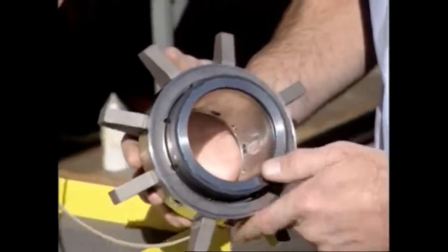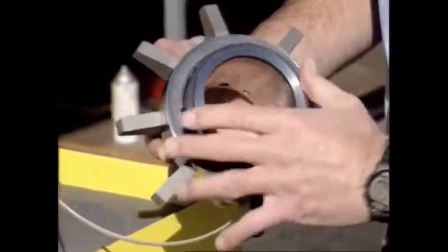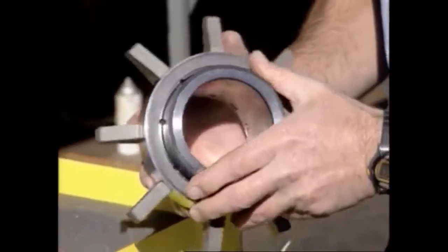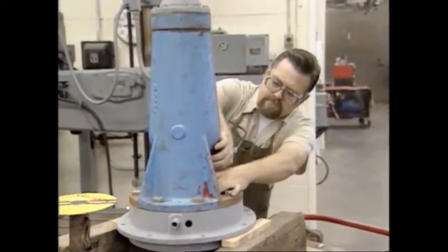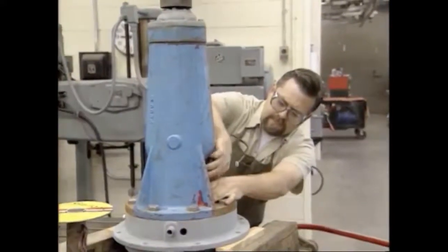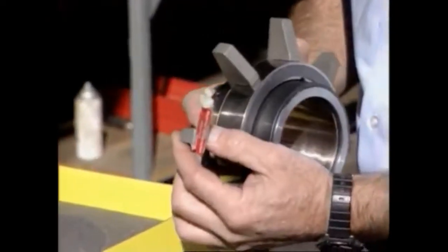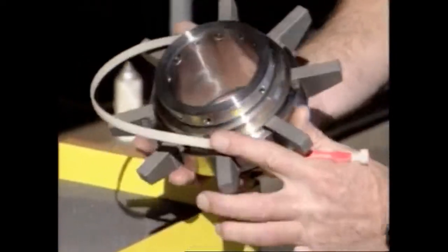Many pumps use mechanical seals in place of packing. Mechanical seals perform the same job as packing, that is, to prevent leakage between the pump casing and the shaft. Like packing, they are located in the stuffing box where the shaft goes through the volute. They shouldn't leak. That's one of the reasons why mechanical seals are gaining popularity in the wastewater field. Mechanical seals have two faces which mate, preventing water from passing through them. One half of the seal is stationary, and the other half revolves with the shaft. Some of the variables are liquid and solids being pumped, shaft speed, temperature, corrosive resistance, and abrasives.